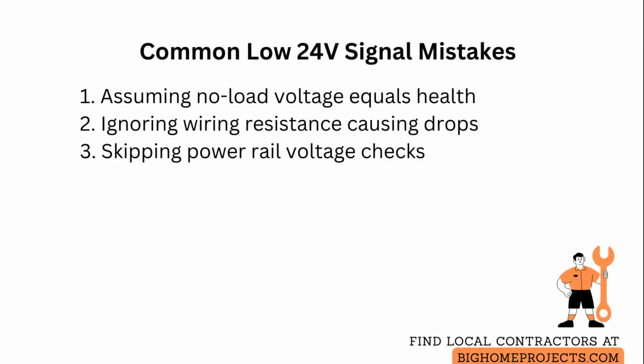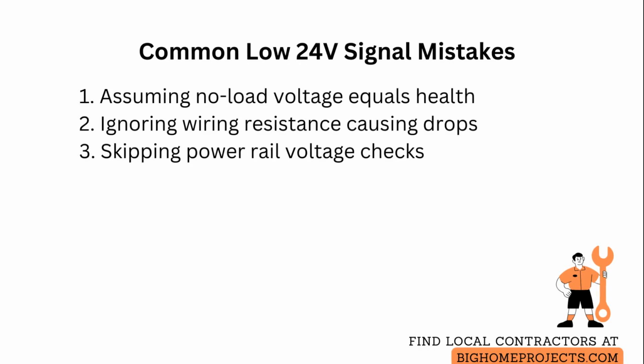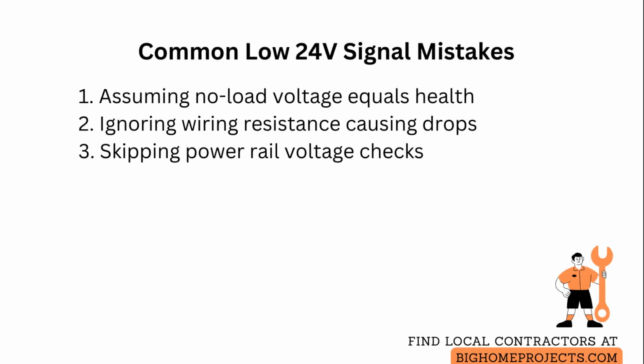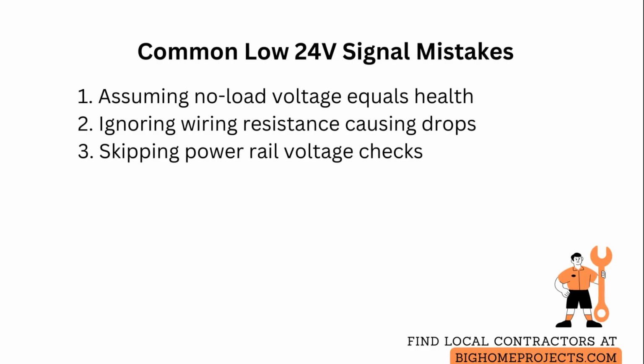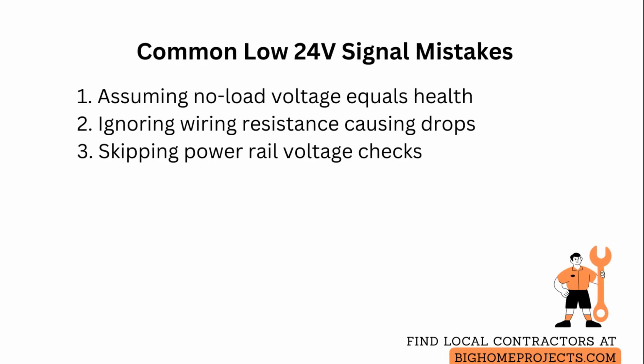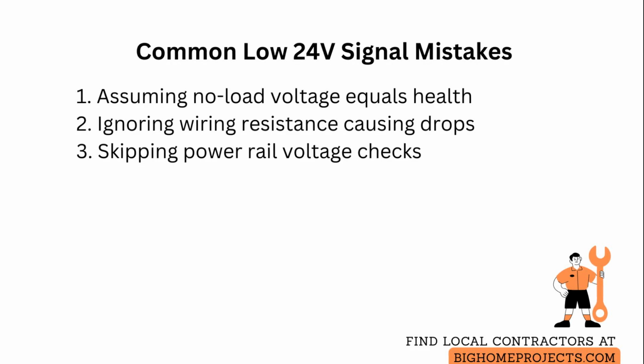Common mistakes include assuming a healthy no-load voltage means the supply is fine, which leads to missed under-load voltage collapse. Measure under load and replace undersized transformers to fix this.